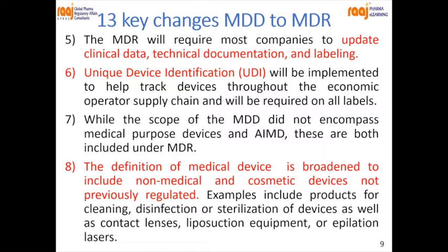Then there is a unique device identification, which identifies your medical device, and will be implemented to help track the device throughout the economic operator supply chain and will be required on all labels. What does it mean, throughout the economic operator supply chain?